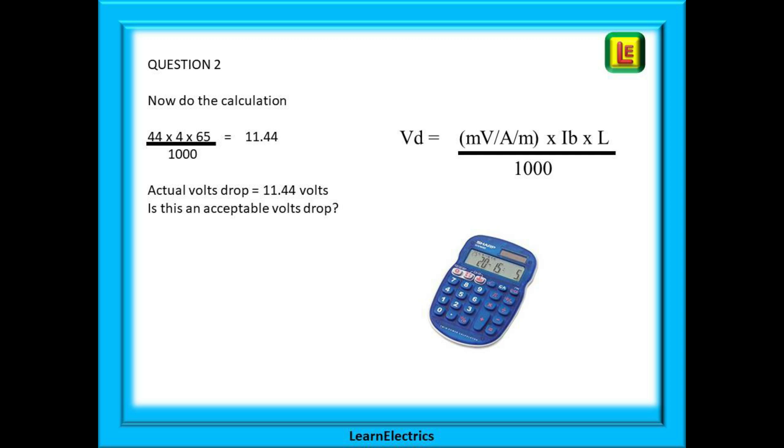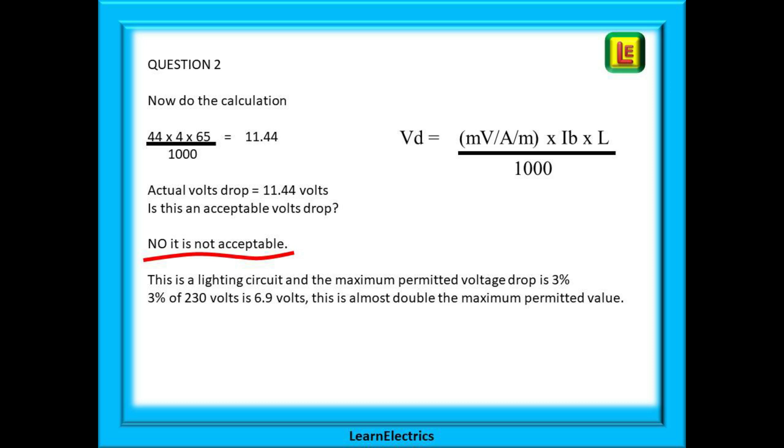44 multiplied by 4 multiplied by 65 and divided by a thousand equals 11.44. So the actual volts drop is 11.44 volts. And the second part of the question: is this an acceptable voltage drop, is it less than the permitted maximum? The answer is no, it is not acceptable. This is a lighting circuit and the maximum permitted volts drop is three percent or 6.9 volts. The actual volts drop is almost double the maximum permitted value. In the exam, always make sure of what type of circuit it is, and the question will always tell you.